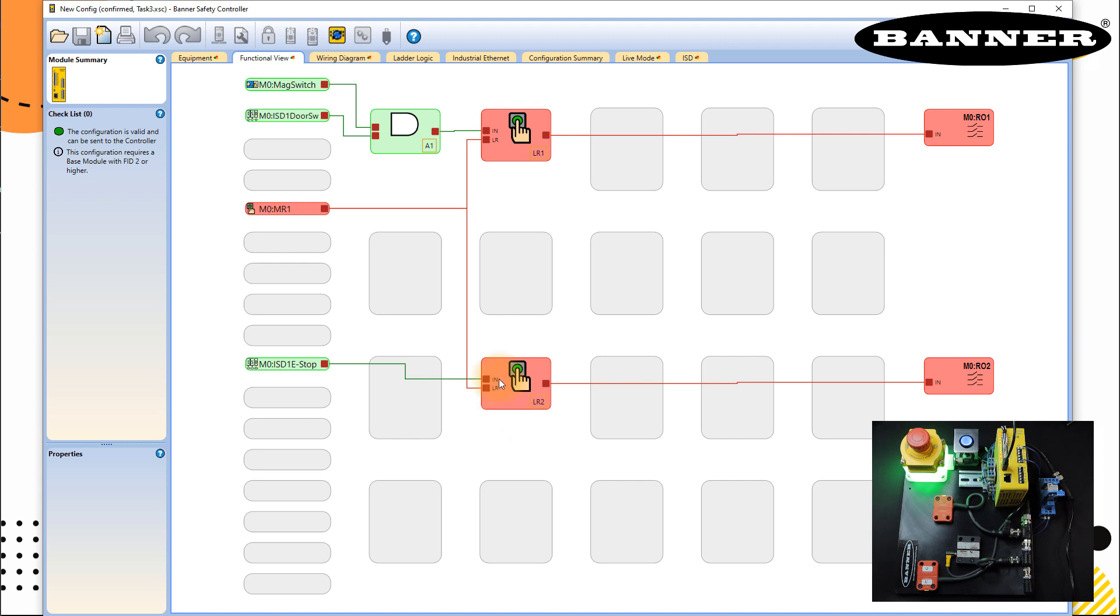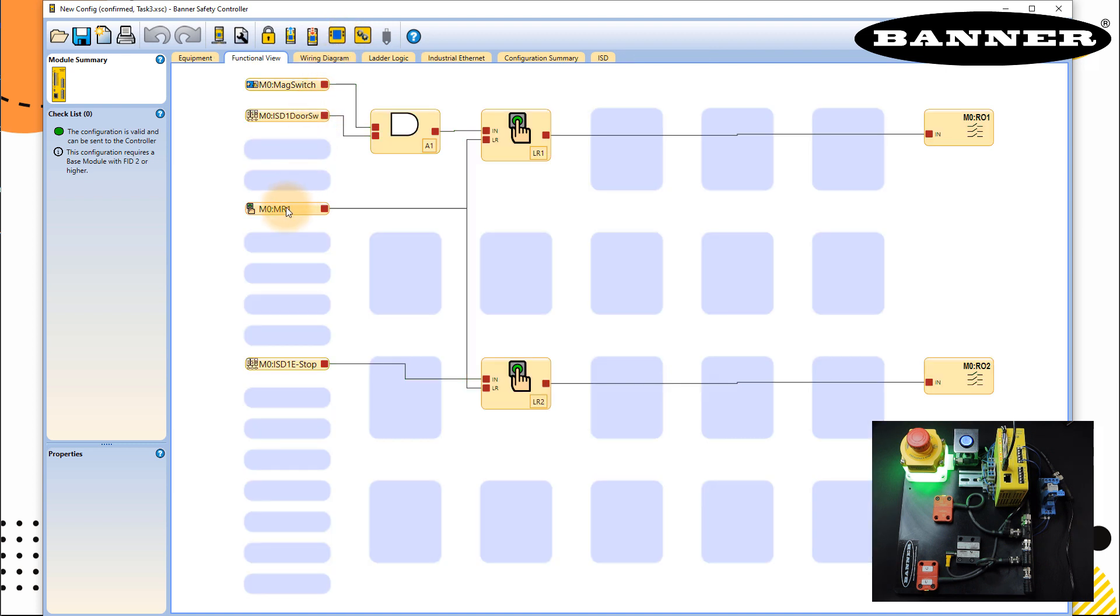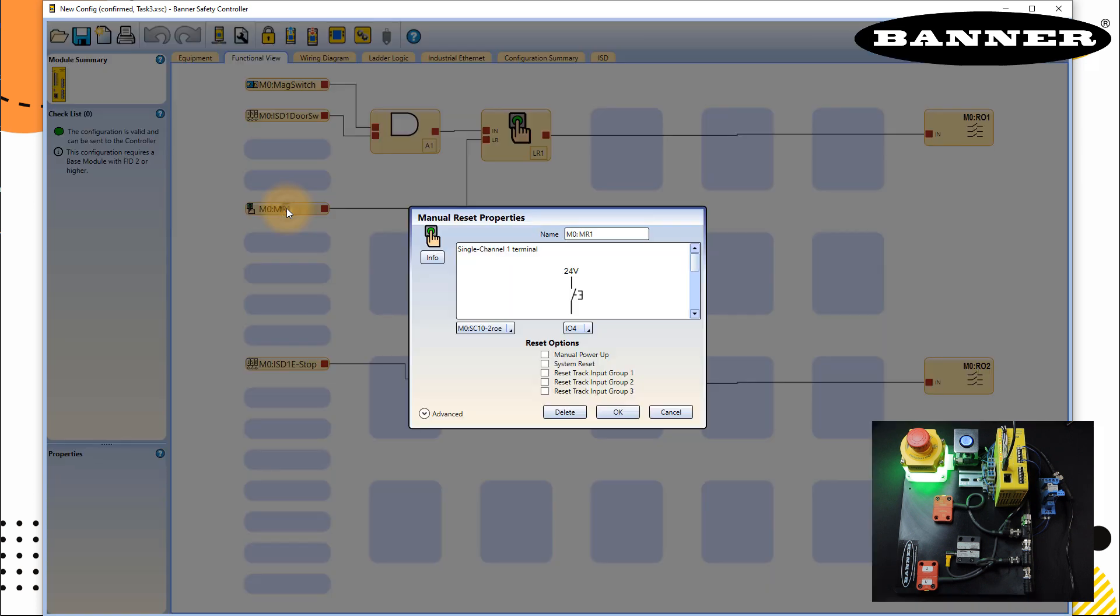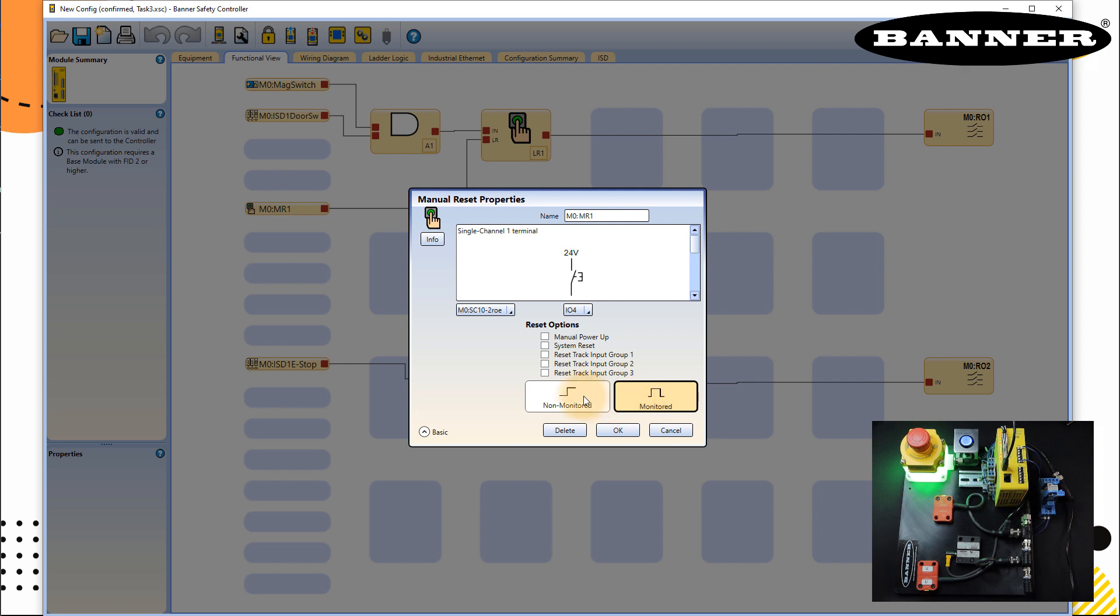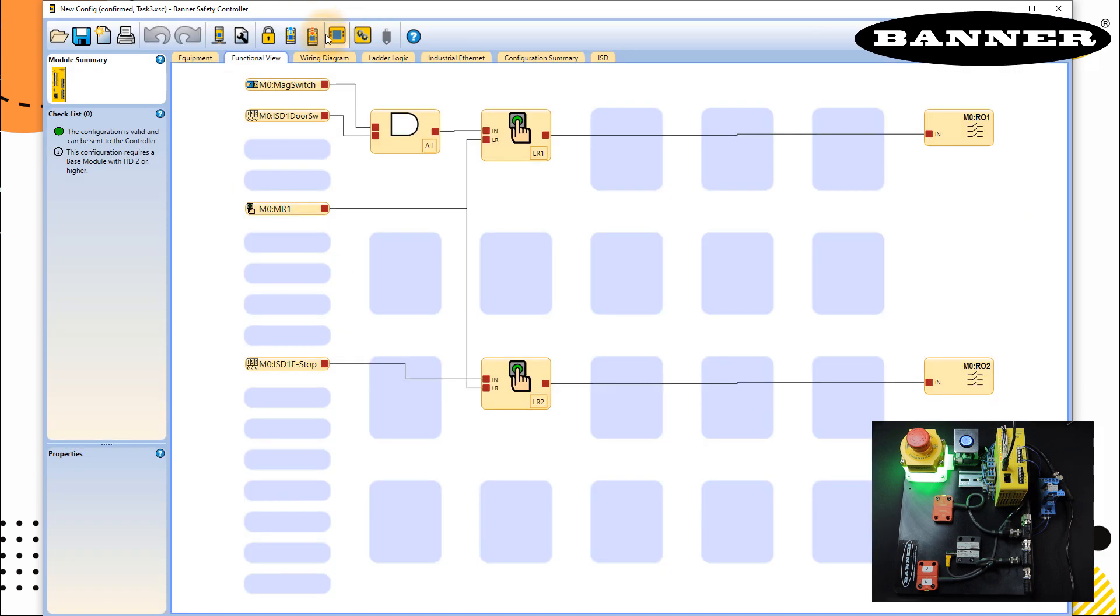And one more thing I forgot to explain before we try this circuit. This input M0MR1 have two types of configuration. So if I go to advanced, it has non-monitored and monitored mode. In monitor mode, it will monitor that the input should be on between 0.5 to 2 seconds. If input is on less than 0.5 seconds, it will ignore that. If input is on more than 2 seconds, it will ignore that. It has to be between this time. And this time is by default in this controller. Non-monitor will not monitor this configuration. It will just monitor if the signal is true or not. So this is right now on monitor.